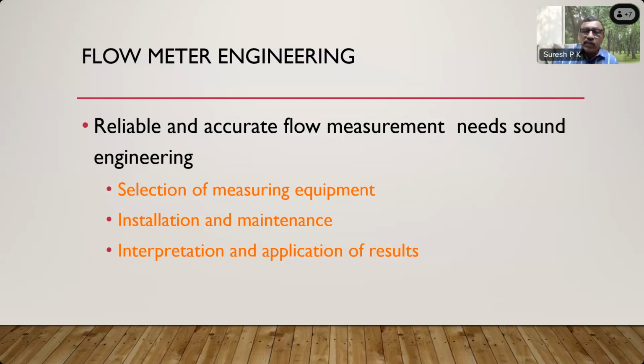So there comes the term upstream, downstream, straight lengths. They call it straight lengths. As we have discussed, the flow can be measured properly if the fluid and the flow are treated properly. If the fluid and the flow are not proper, then you are not going to get an accurate flow measurement. Therefore, the method is, if you have, for example, multi-phase flow, so some air is getting into your liquid, then you have air removers in the flow line, which will remove the air and then send it to the flow meter for measurement. You attach to certain flow meter.